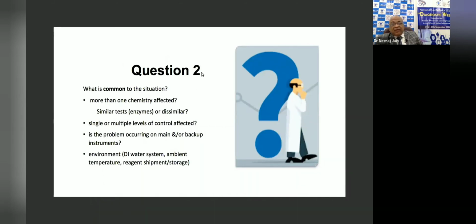Suppose more than one chemistry is affected, whether you are performing these on the same filter or on different filters, or all are kinetic, or all are endpoint, so we have to see, or whether a single level control is affected or multiple level controls are affected. And also see environmental conditions, whether the water system pH and resistivity are okay, whether ambient temperature is okay, and who accepted the reagent, whether everything was okay at the time of accepting those reagents. We have to analyze all these things.